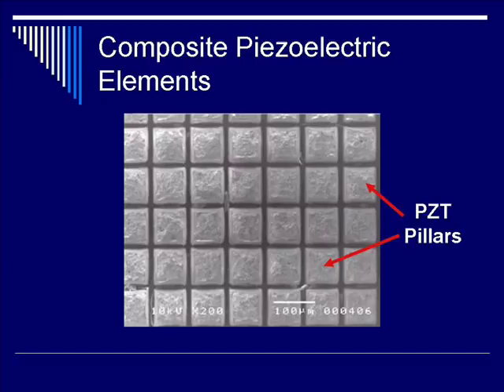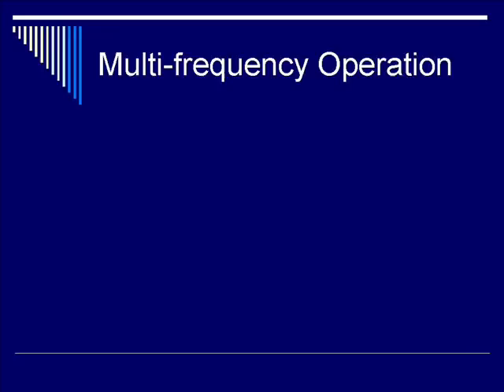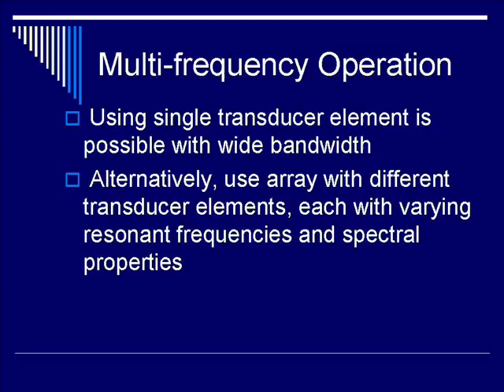For multi-frequency operation, it is possible to use a single layer transducer element as long as it has a wide bandwidth. You can also use an array with different transducer elements and thicknesses, each with varying resonant frequencies and spectral properties.